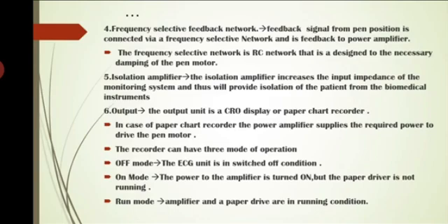Fifth, isolation amplifier. The isolation amplifier increases the input impedance of the monitoring system and thus provides isolation of the patient from the biomedical instruments. Sixth, output unit. The output unit is a CRO display or a paper chart recorder. In case of a paper chart recorder, the power amplifier supplies the required power to drive the pen motor.